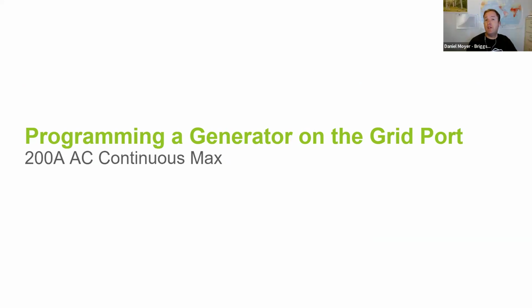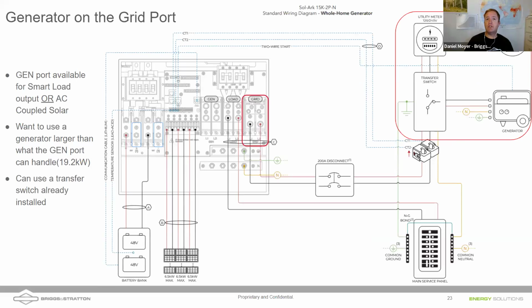Yeah, thank you, Nathan. I think this is one of the keys to the Sol-Ark's capabilities of integrating generators, the idea that we can bring in a generator on the grid port. So what we've got up in the top right corner is our grid, right? The utility, and we're bringing it into a transfer switch. And normally in normal operations, this would be connected here. It would feed 200 amps into grid, 200 amps right back out. If the Sol-Ark detects a grid outage, it's automatically going to isolate itself from grid. Notably, the transfer switch will still be connected to the grid.